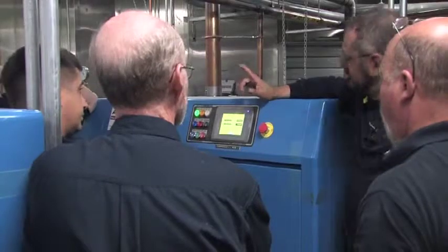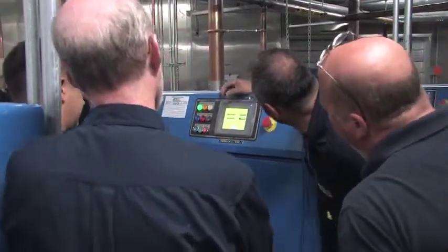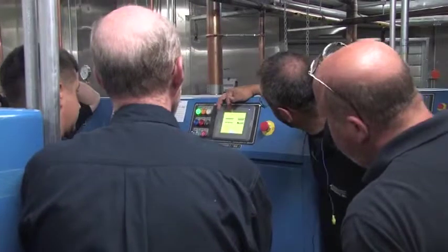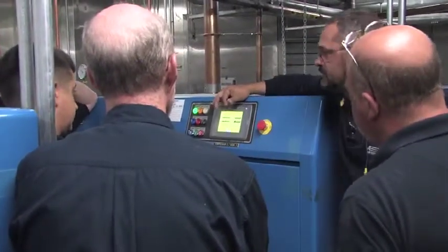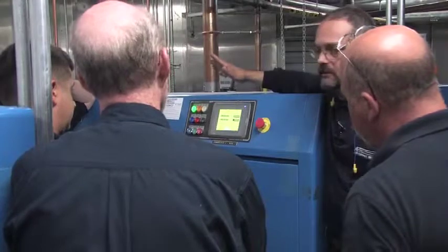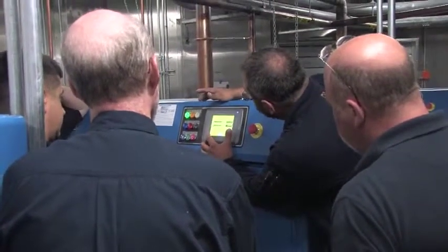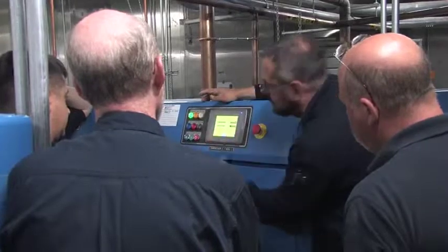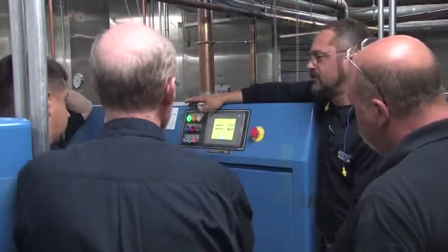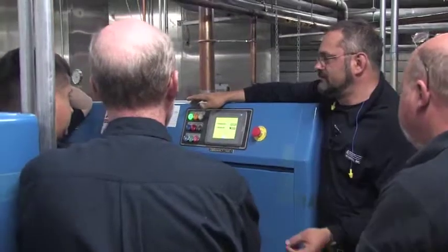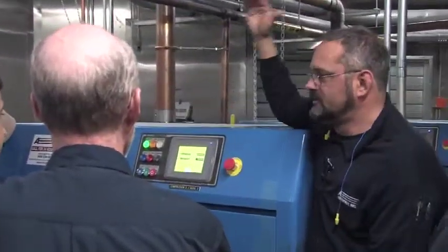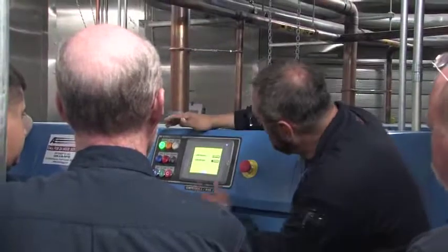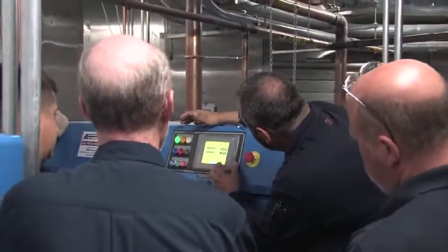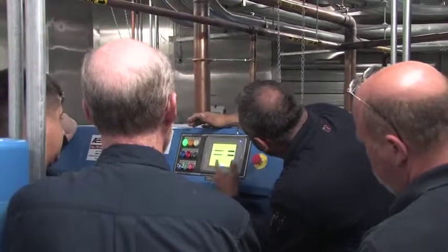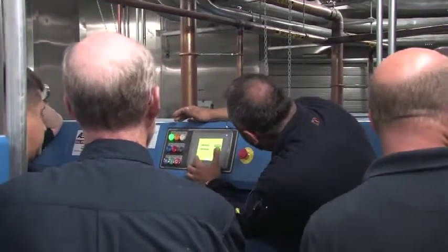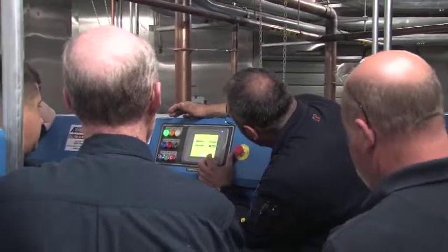That's not true of the pressure sensors. You can see here, the lube transducer is calibrated 0 to 100 pounds. That's the actual range of the transducer they use. The interstage is calibrated from 30 inches HG, so it's 0 psi absolute, to 60 psi. And the discharge is 0 to 160.